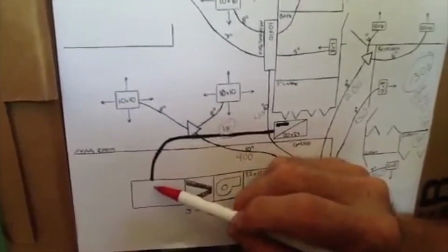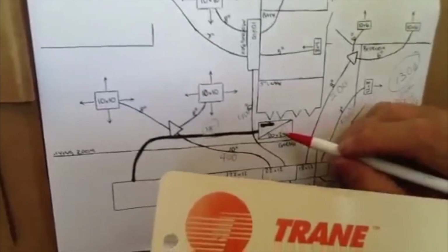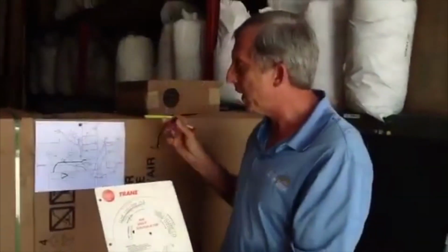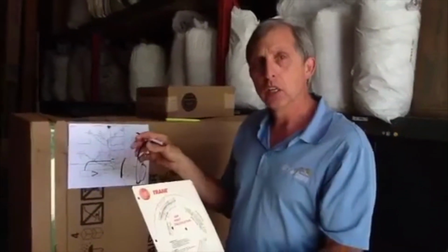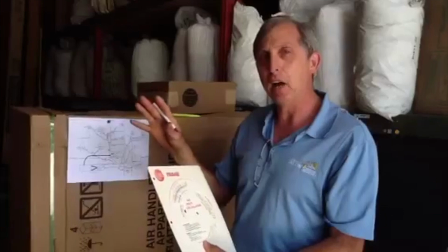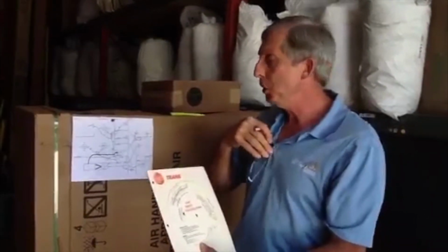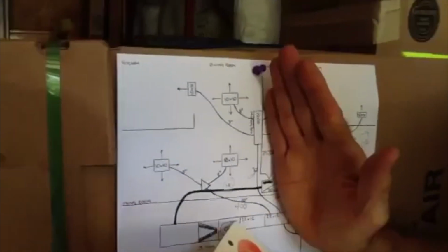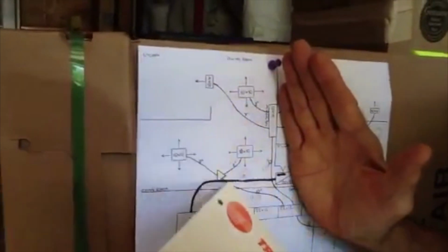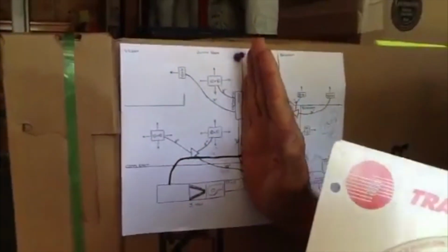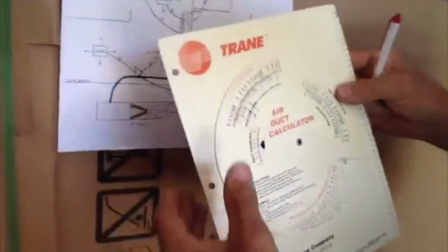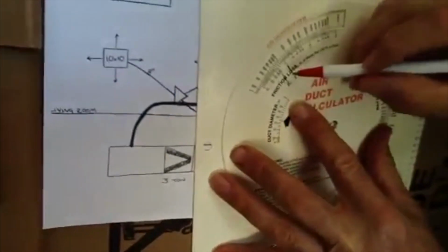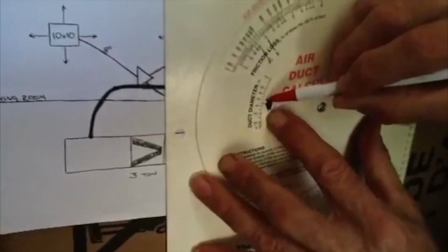So I would pull an 18-inch flex from here to my return grill. Okay, a lot of times what we really try to do in the particular homes, we actually will split up and add 2 returns, sometimes 3 returns depending on the run. And I can show you real quickly how that works. What you would do is basically, let's just say for instance, I'm going to give you a quick example. Let's just say this room here, we have 400 CFMs, 400 CFMs, that's 800 CFMs, right? We know that's 2 tons of the air conditioning right there. So I'm going to go to 2 ton, which is 800 CFMs, 0.05 static pressure, 14-inch. So I'm going to add a 16-inch return here.